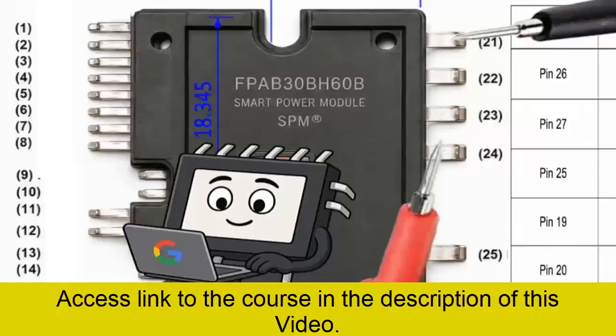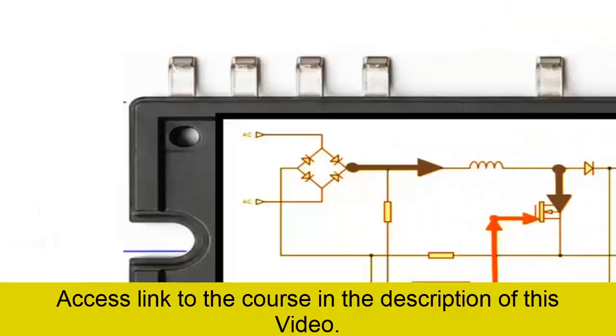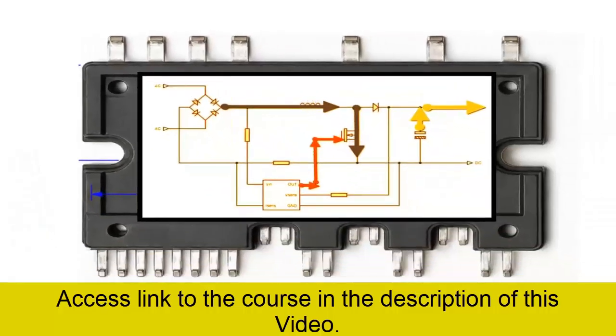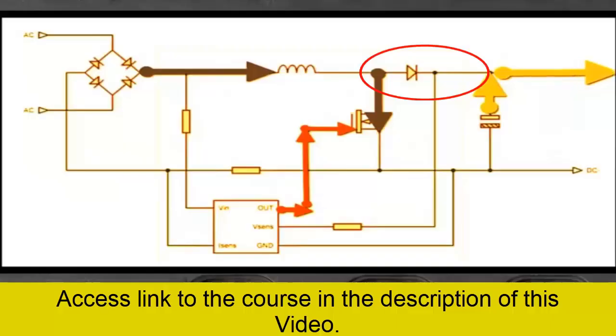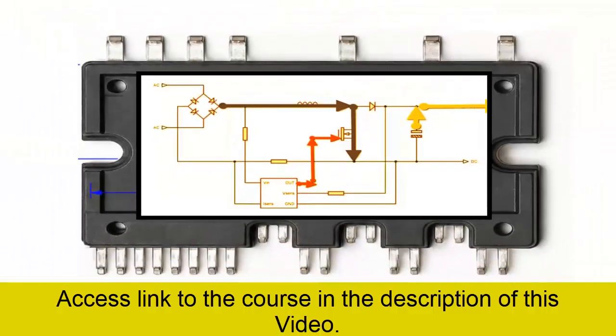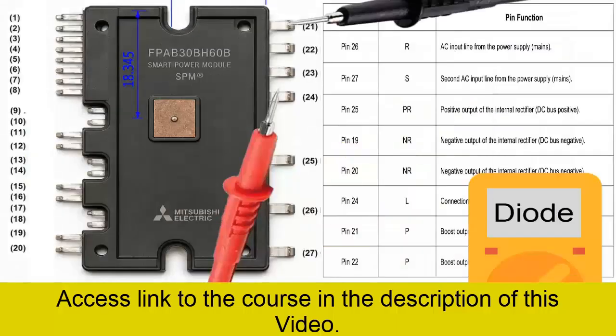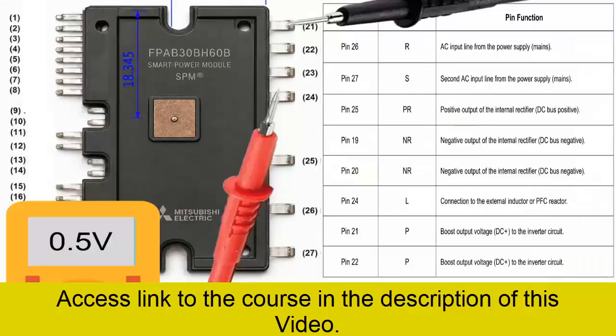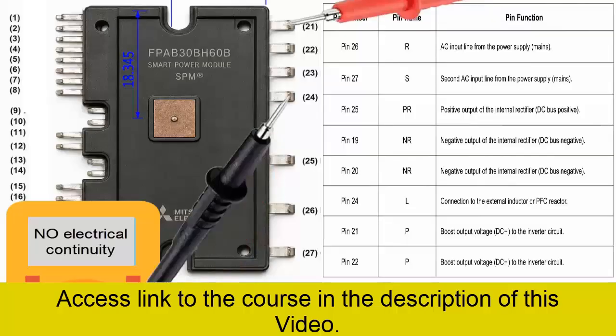Next, the high-speed diode test of the boost circuit is performed. This test allows verification of whether the internal fast diode correctly delivers the high current to the main DC bus capacitor. Step A: place the black probe of the multimeter on pin P and the red probe on pin L. Correct reading: the multimeter should display a diode drop voltage of approximately 0.3 to 0.5 volts. Step B: reverse the probes by placing the red probe on P and the black probe on L. Correct reading: the multimeter should indicate an open circuit or absence of continuity.